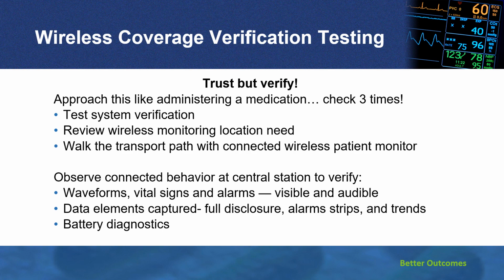What is the need? Walk that transport path with a connected wireless monitor, and also have somebody back at the hub, where there could be a central station, so they can verify your connectivity. Do they see that waveform during the transport? Are the vital signs still flowing? Are they hearing any alarms, if you could simulate them, either visibly or audibly? What data elements are being captured during this transport? You should be seeing full disclosure, alarm strips and trends, and there should be a way to understand how the battery is. Depending on which device you are able to bring with you, you may need to pack in your little goodie bag an extra battery in the event that battery would die. So both on the actual devices themselves and then back at the ICU station, you can check those types of things. So always trust and verify before you go off on your first adventure with the patient.